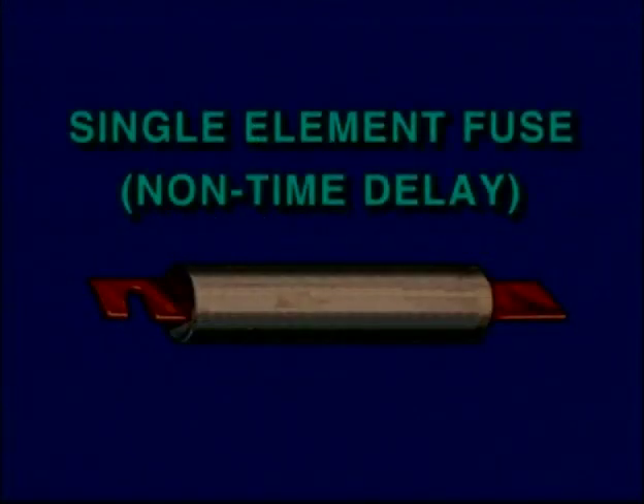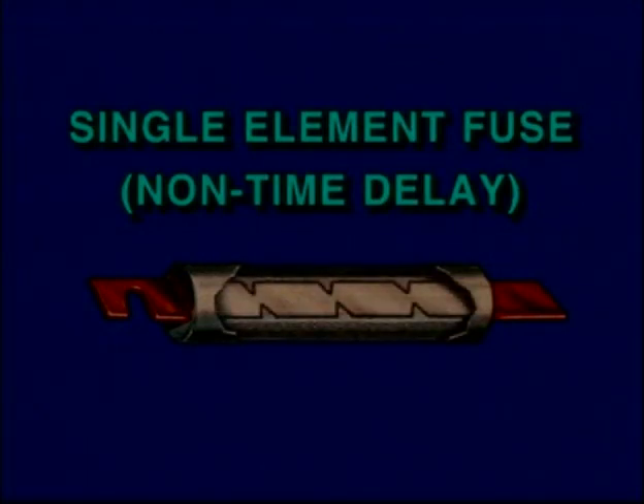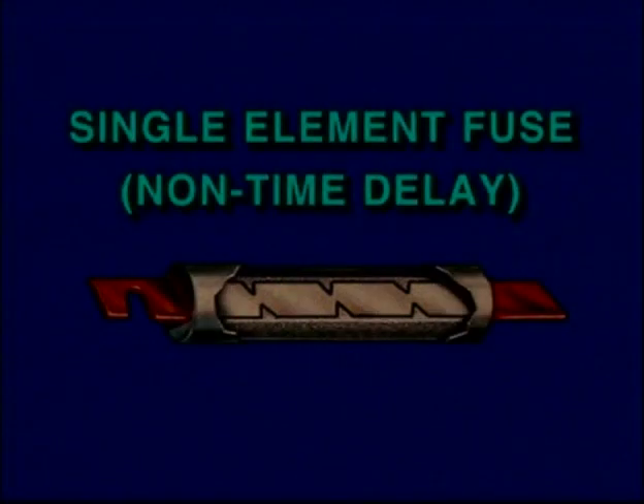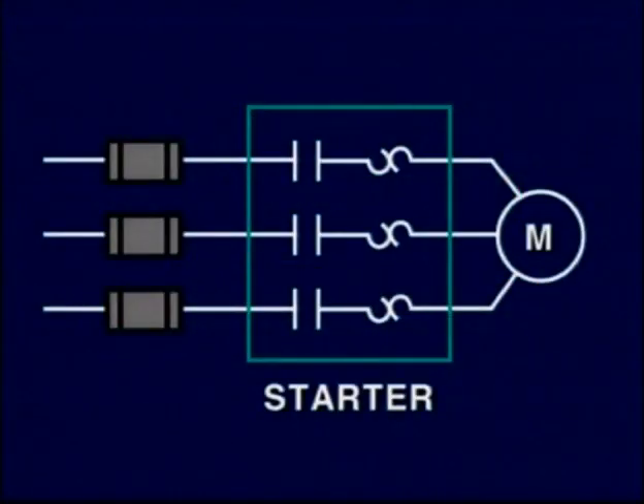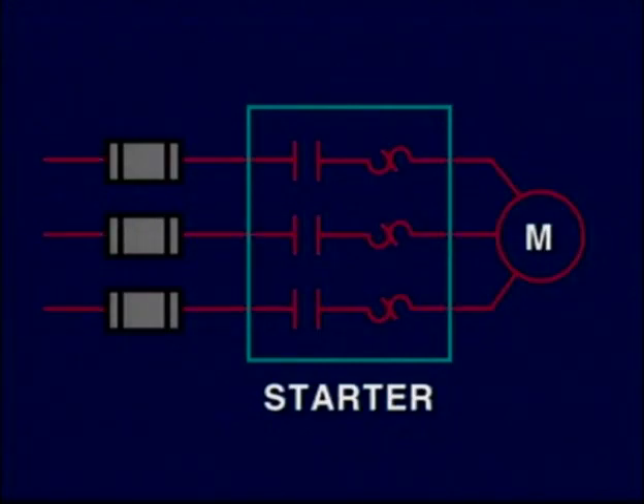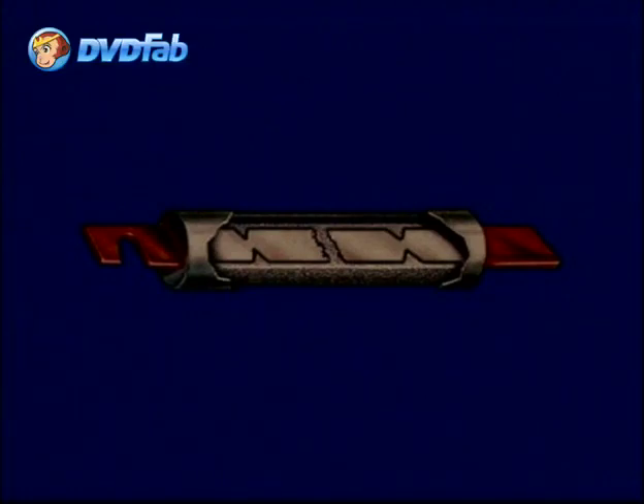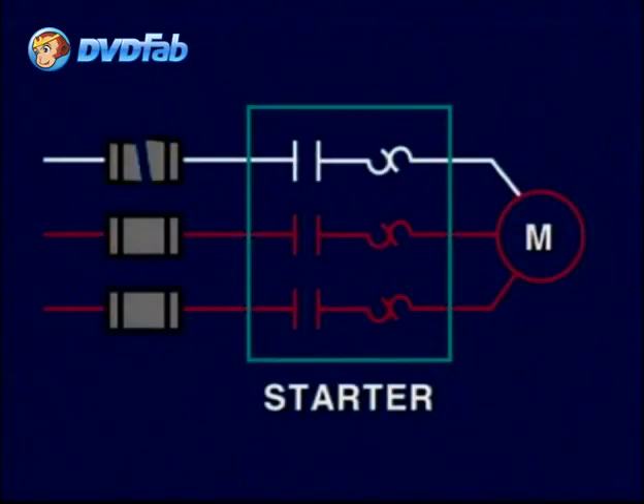The single-element fuse, also called a non-time delay fuse, is made of one conducting element which has one or more links enclosed in a tube or cartridge surrounded by arc-quenching filler material. Under normal operation, the fuse conducts current simply by acting as a conductor. If an overload occurs and persists for a short interval, the temperature created by the overcurrent reaches a level which melts the link and a gap is formed, thus breaking the circuit.